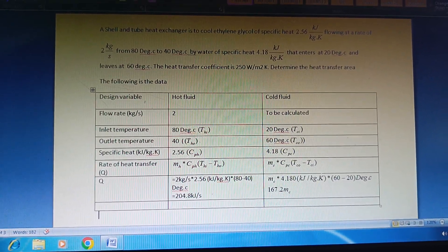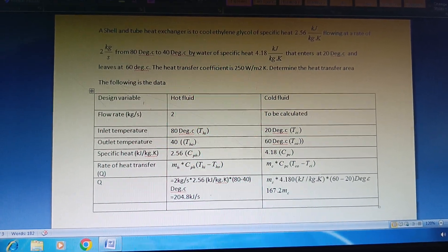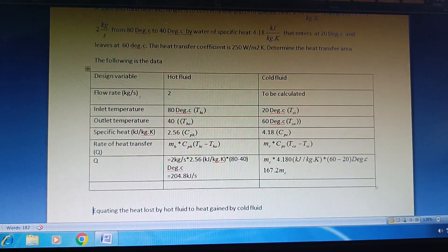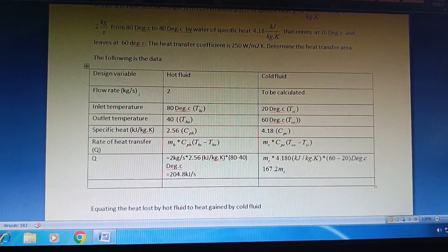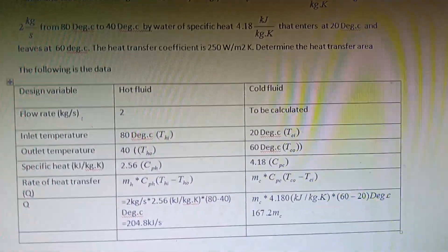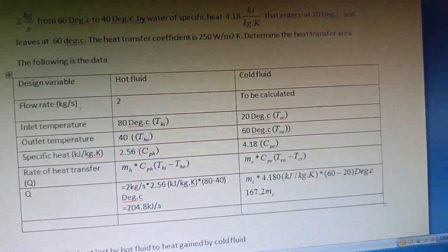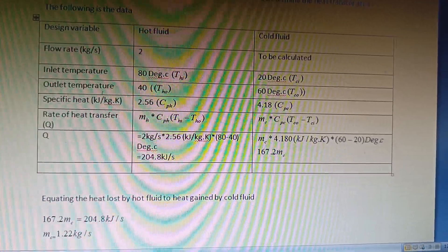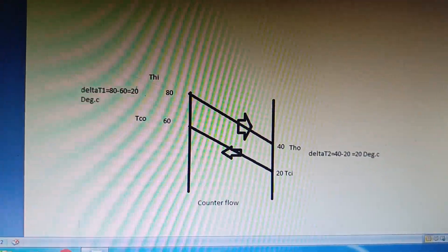All this heat must be transferred to the coolant. For an adiabatic system — one where there is no heat gain or loss from the surroundings — we equate the heat lost by the hot fluid to the heat gained by the cold fluid. This gives us the mass flow rate of the coolant, which is one of the design parameters, and that works out to 1.22 kg/s.